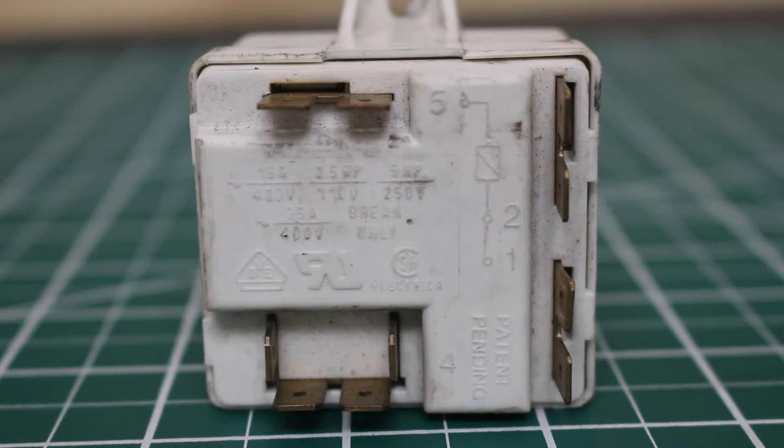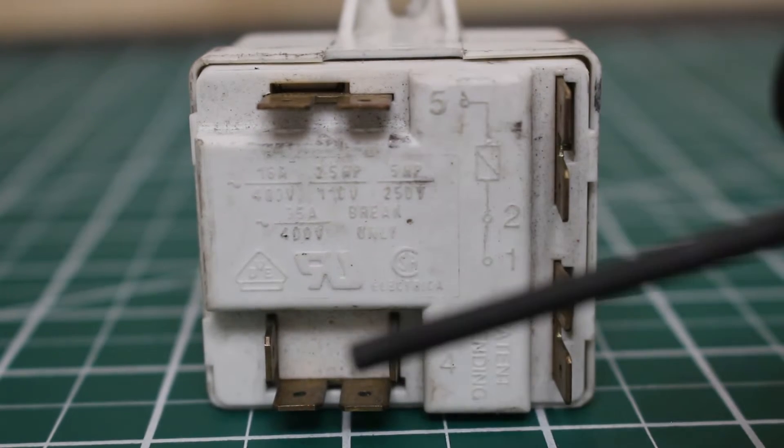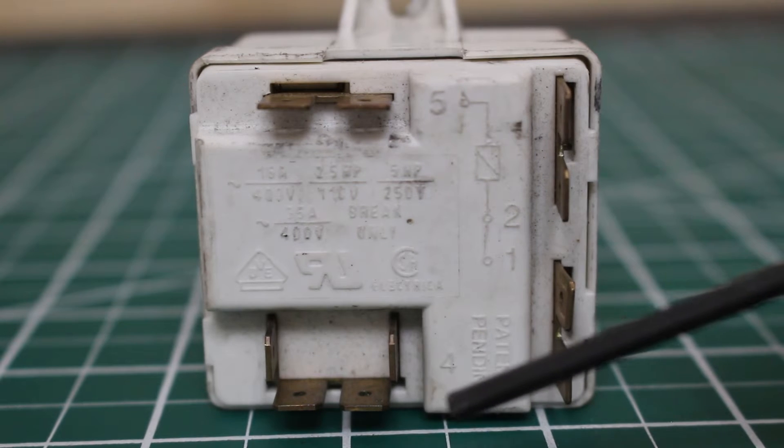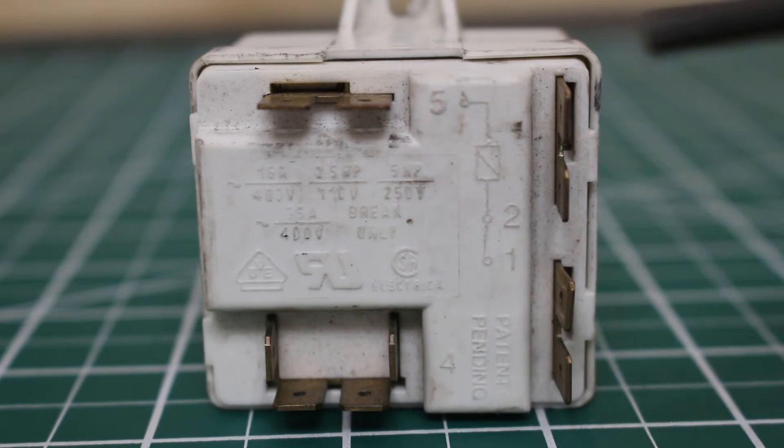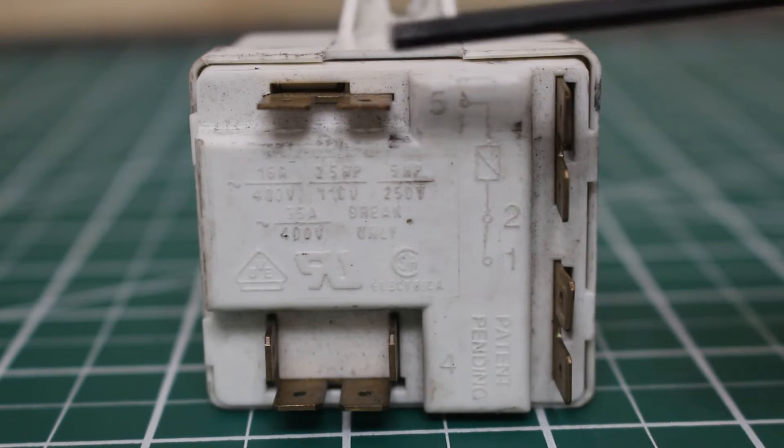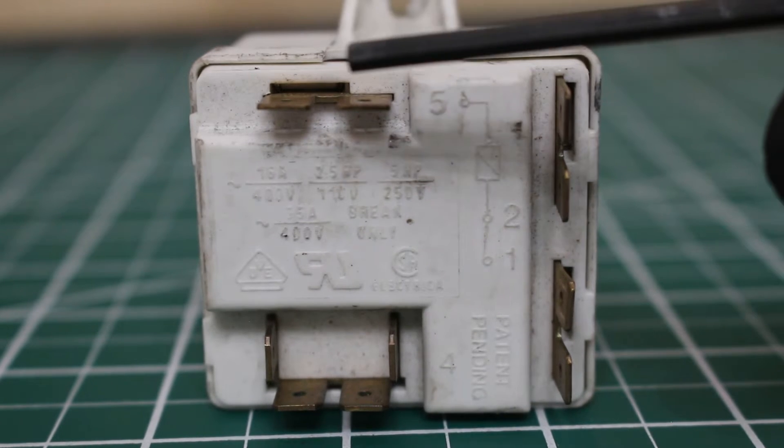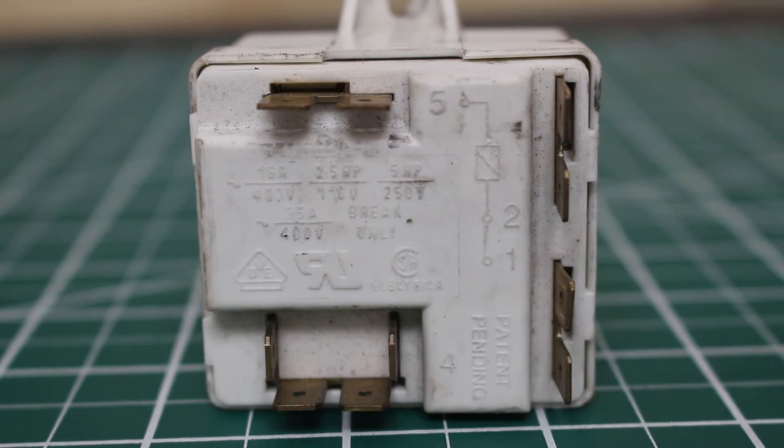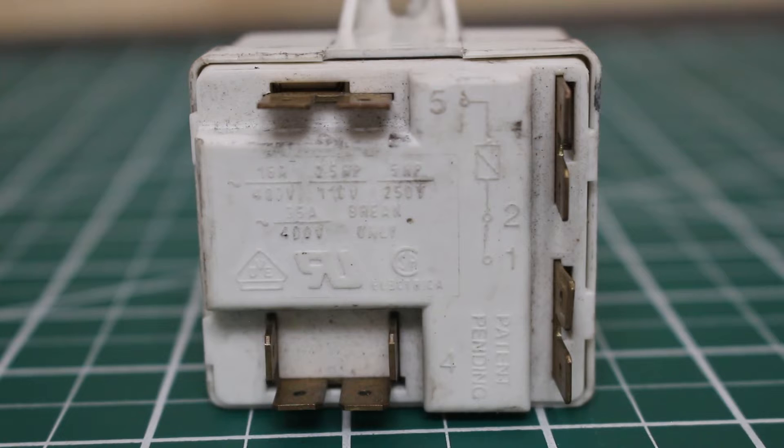One thing that really struck me as strange earlier in my career was this extra terminal. You see we have it labeled as 4. Sometimes you also see a 6. This has nothing to do with the relay, and it's honestly a dummy, a dummy point. So you can just disregard this. The only thing you'll be checking in this relay is points 5, 2, and 1. And this works for every single type of relay that is on the market.